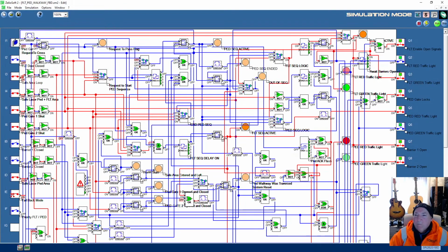Right. Okay. So now the barriers, let's see what the barriers are doing in this fallback mode. Let's give it a sequence. Now they're opening, they're actually still operating, aren't they? The barriers. Well, the outputs are going on, but there's no activity being detected. Yeah, they're not detecting this area in fallback mode. Yeah, they're not relying on that to switch.